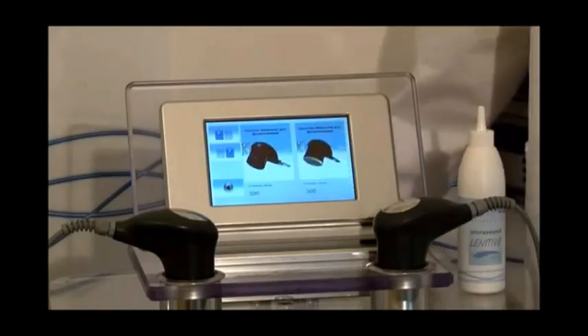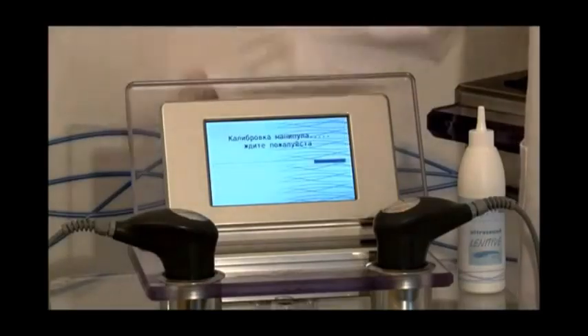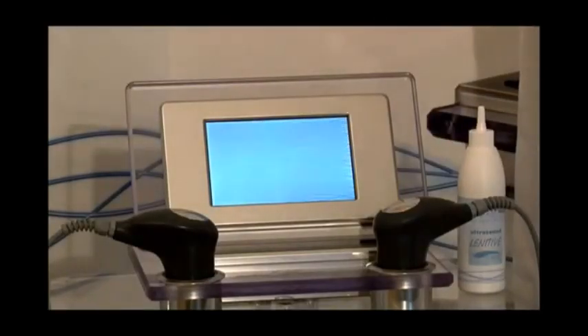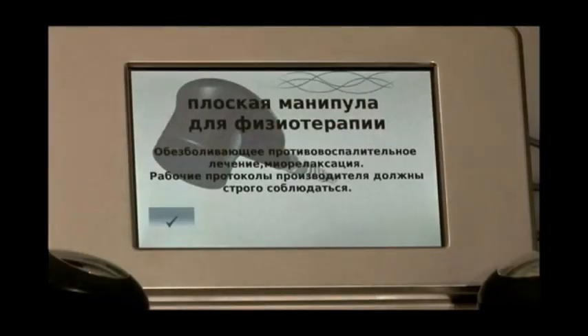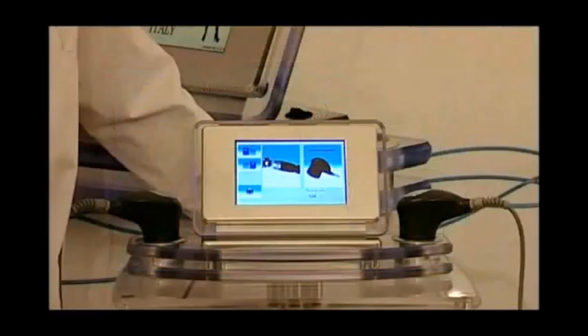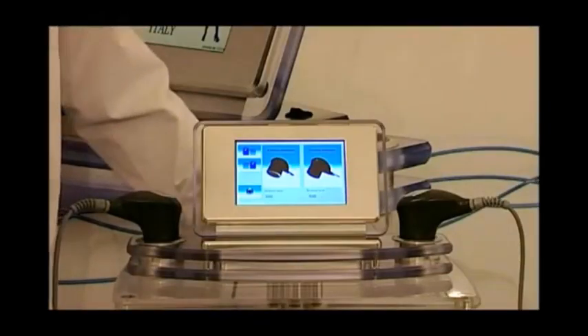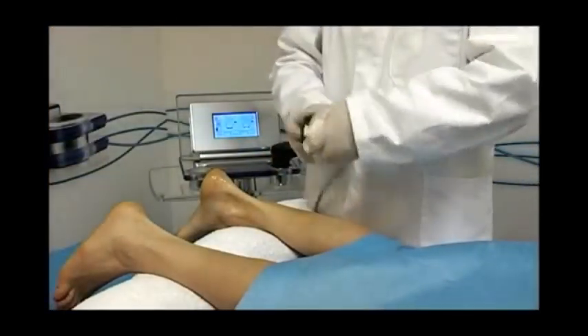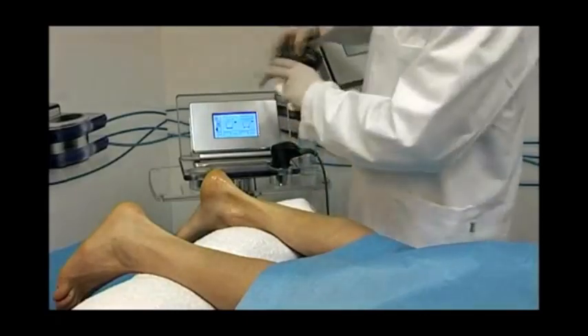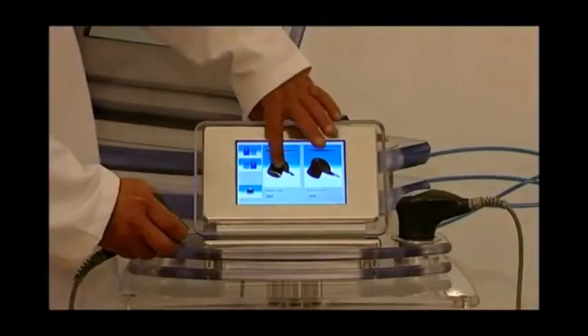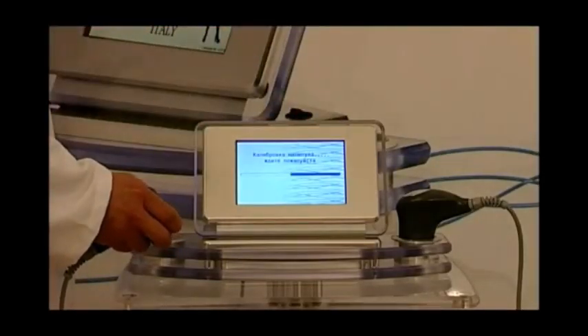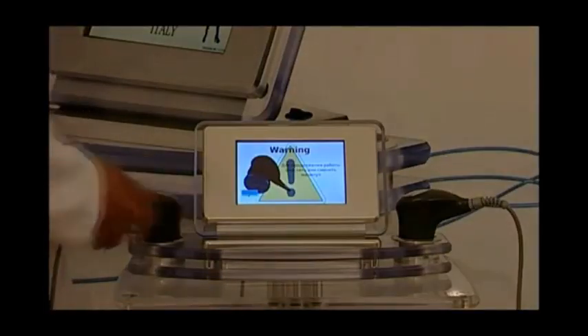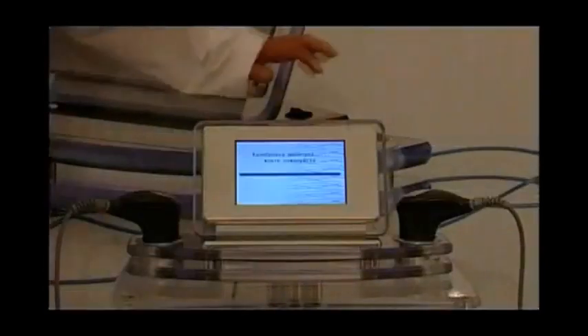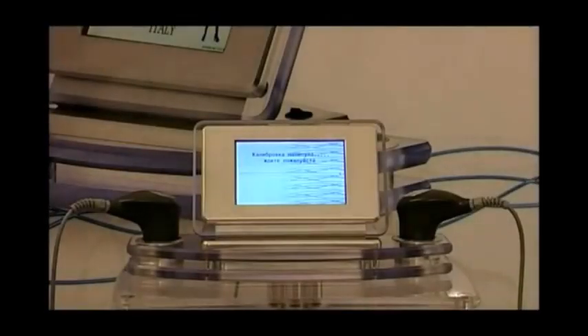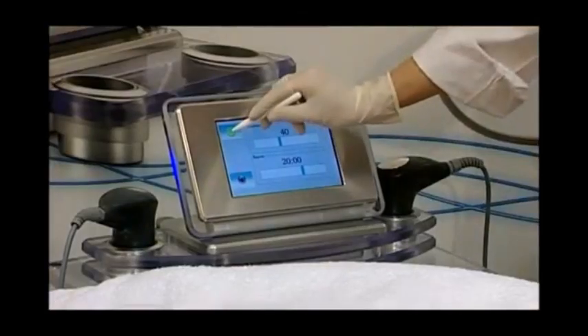In order to start the treatment, it is necessary to select the hand probe you wish to use first. During this check, the device verifies the hand probe's conditions and enables its use. Press on the check mark to proceed to the treatment phase. The device also performs a self-recognition check for the connected hand probe. Hand probes must always be clean and must be inside their housings during the self-calibration phase. As you can see, we've simulated some types of failures. In any case, the device prompts the user to repeat the self-calibration phase. When treatment starts, the default factory ultrasound power output is set to 40%.